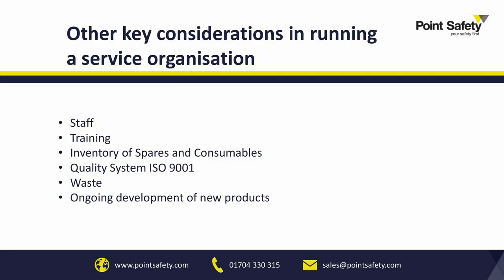Sensors have a lifetime, so you need to predict how many you're going to require each month, because you will not want them sitting on the shelf or in the refrigerator in many cases, because they do deplete even while being stored. So you want to give the maximum life once they are installed and you're putting them into your customers' meters. Again, quality systems. I'd always recommend at the very minimum that any service organisation would have an audited quality system such as ISO 9001. This allows you to ensure that your processes, both internal and external, are followed, as well as any warranty repairs, warranty returns back to the manufacturers. It gives a good grounding. It also gives confidence to your customers ongoing.